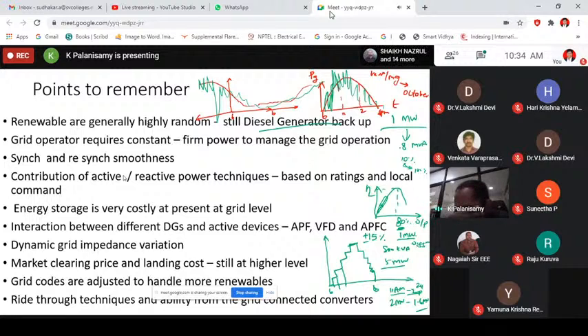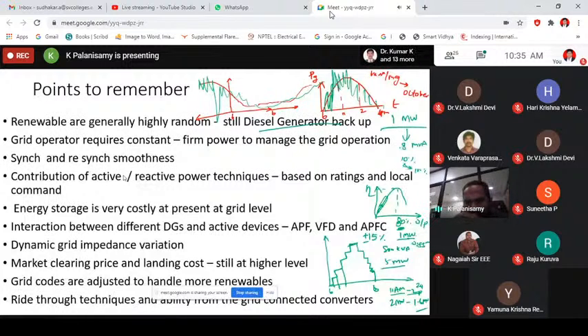Of course, most of you must have studied or experienced the LCL filter. Nowadays the solar PV, active power filter, or any VFD is coming with an LCL filter, right? The LC, of course, we all know, is to suppress the switching frequency. There will be a switching signal, and to reduce that switching impact on a weak or reasonably strong grid, they connect the LC filter. That is very common, of course, we have studied it in power electronics. But the recent technology is the LCL filter. In the LCL filter, the LC is our side, and the other L is from the grid side, right?